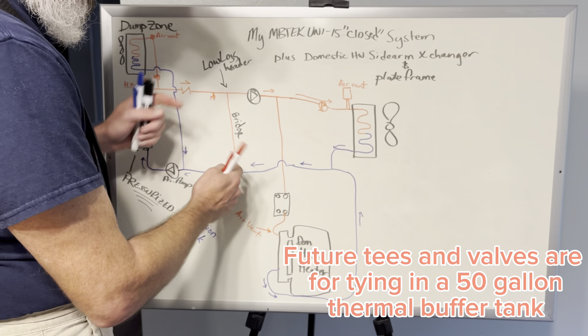In commercial applications, you would call that a decoupling bridge. In my system, I have two pumps. I've got a pump here, that's the primary side, or the boiler side. And then I have a pump over here, that's the secondary side, my house side, the load side. Once the water gets up to temperature in the boiler, this pump is going to come on first, and it's just going to start moving water around this way. So this is open. Now, it's a low loss header. Like I said, I may do a video about that. You can just Google what a low loss header is, or a decoupling bridge.